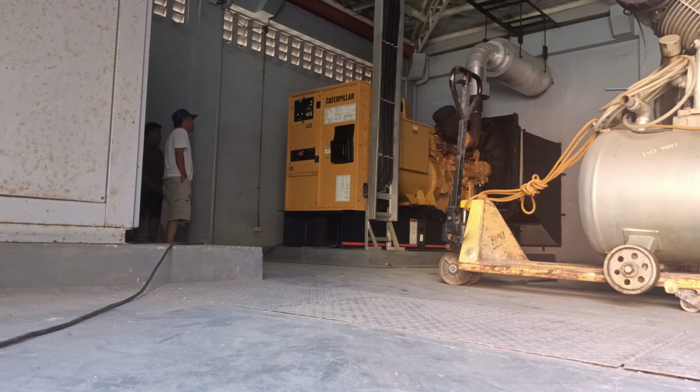With the generator testing completed, the focus now shifts to testing the remaining production generators. To optimize costs, a single pair of batteries is being used across all 6 units, ensuring efficient resource utilization. Since none of the generators are currently in operation, only storage testing was conducted to verify their condition and readiness for future use.